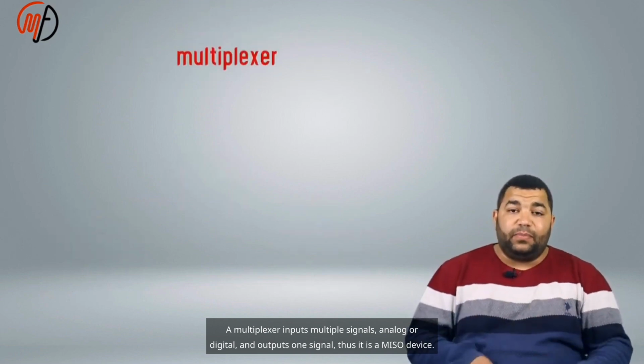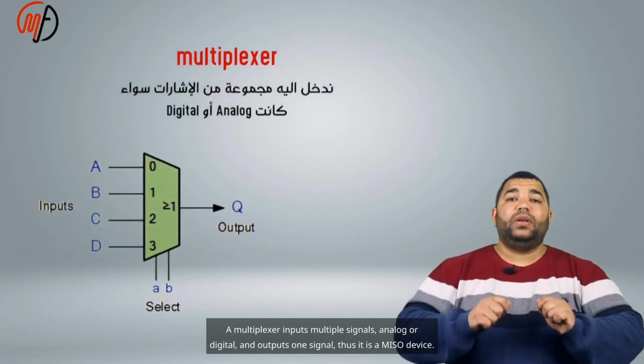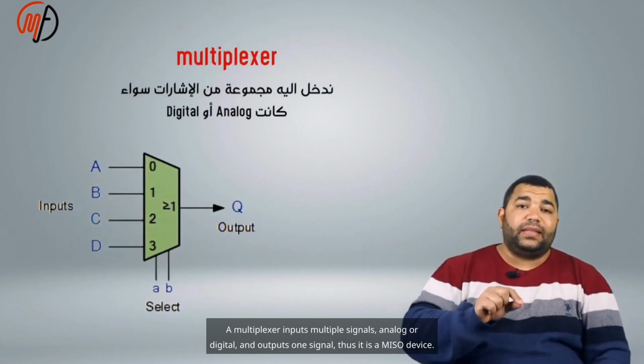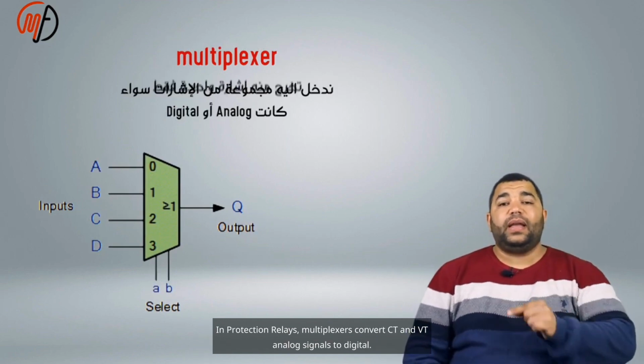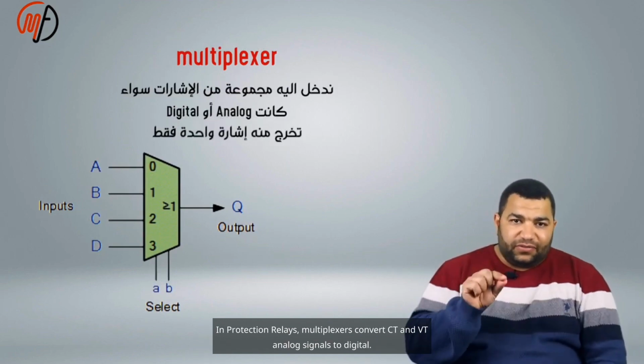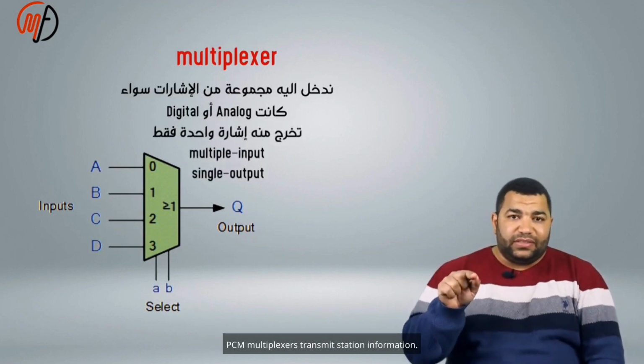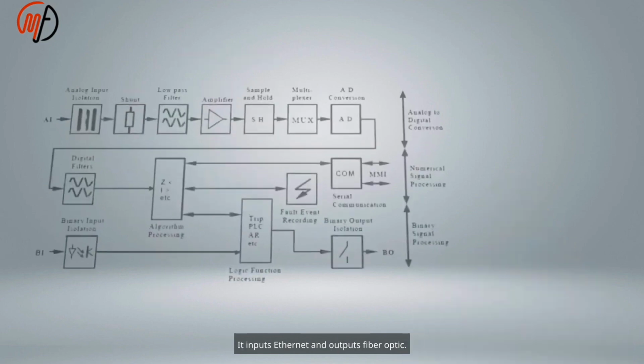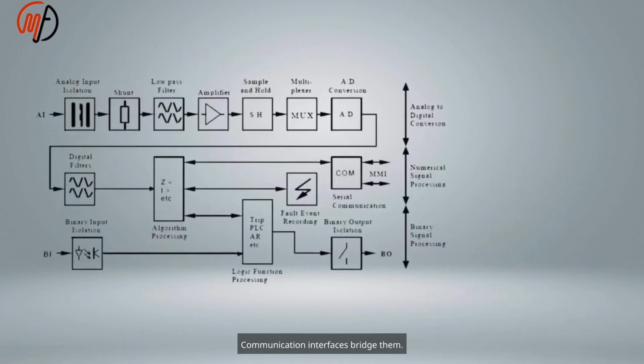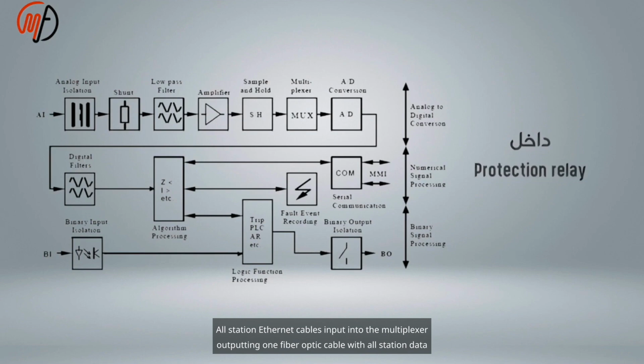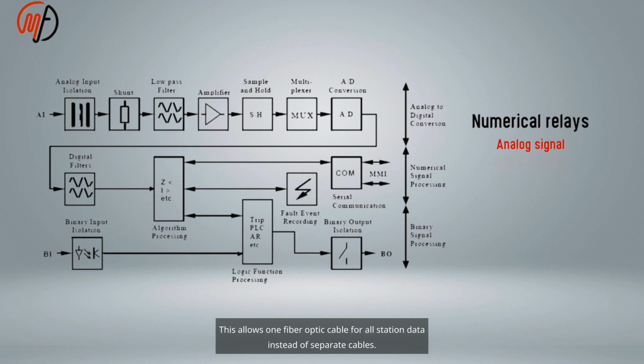A multiplexer inputs multiple signals, analog or digital, and outputs one signal. Thus, it is a MISO device. In protection relays, multiplexers convert CT and VT analog signals to digital. PCM multiplexers transmit station information. It inputs Ethernet and outputs fiber optic. Communication interfaces bridge them. All station Ethernet cables input into the multiplexer, outputting one fiber optic cable with all station data. This allows one fiber optic cable for all station data instead of separate cables.